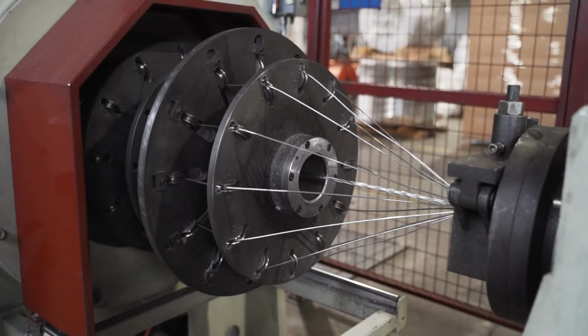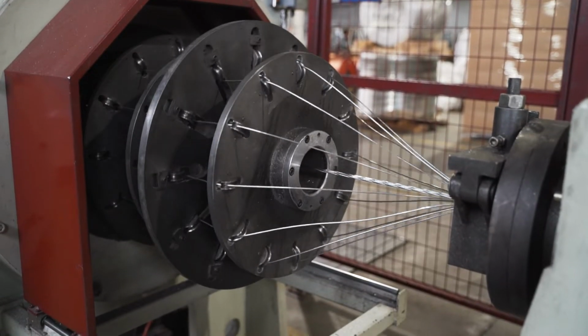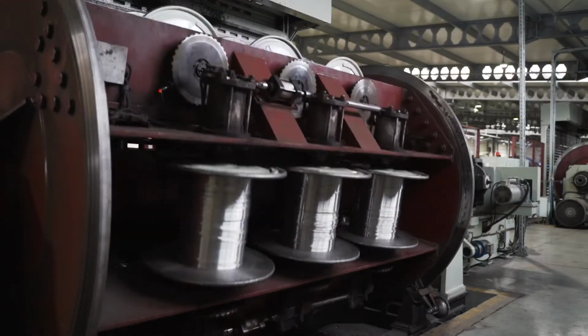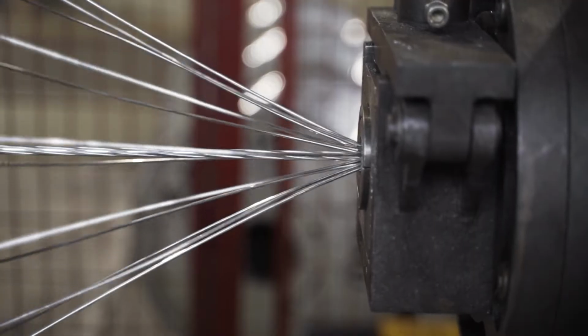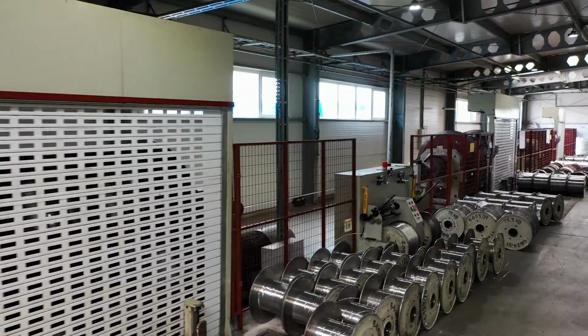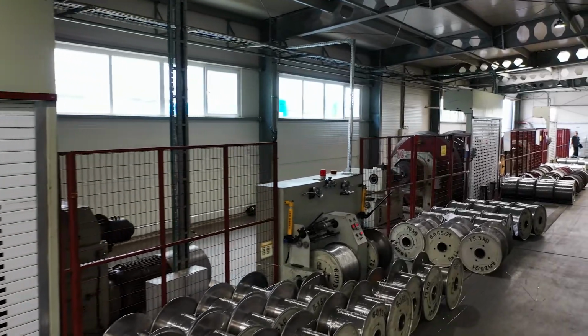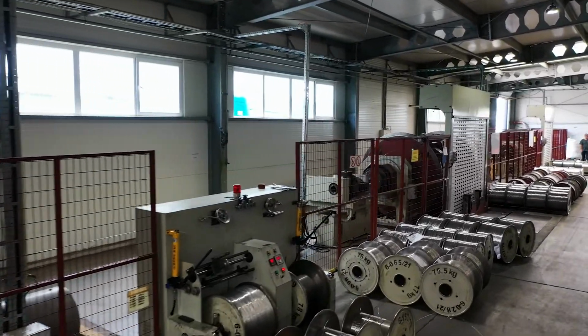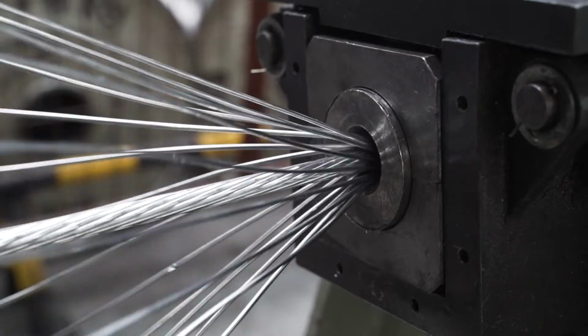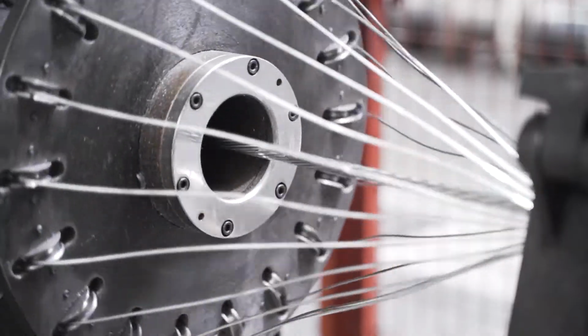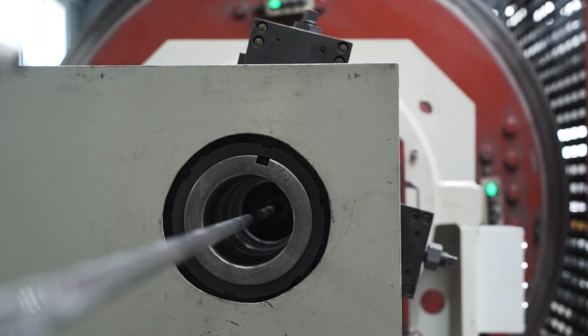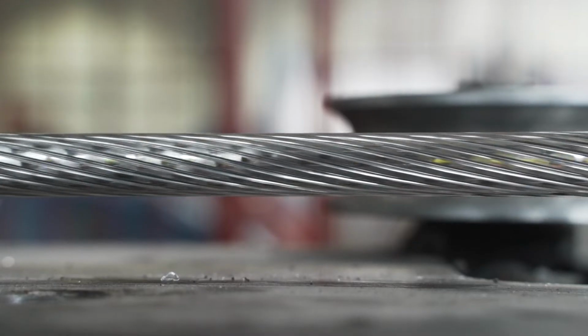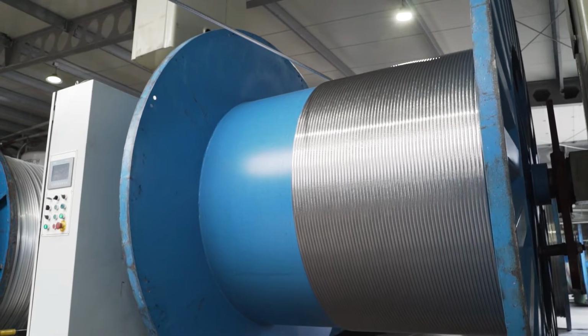Wires must be twisted together to make a conductor. For medium voltage cables, we need from 7 to 61 wires. The wire spools are mounted, and when the line starts, they unwind and enter the calibrator unit, in which they are twisted and compacted. The conductor is reeled on a spool with a diameter of 3 meters and passed on to the next stage.